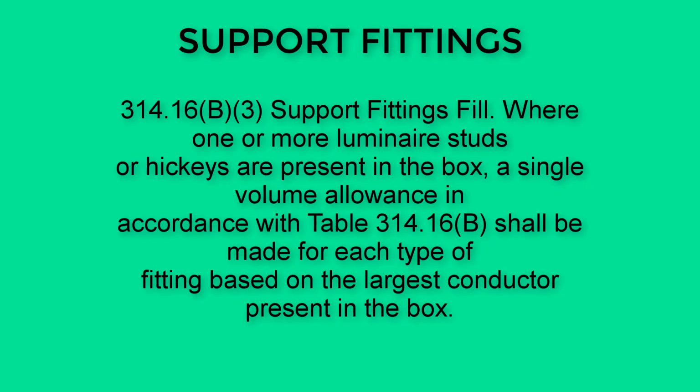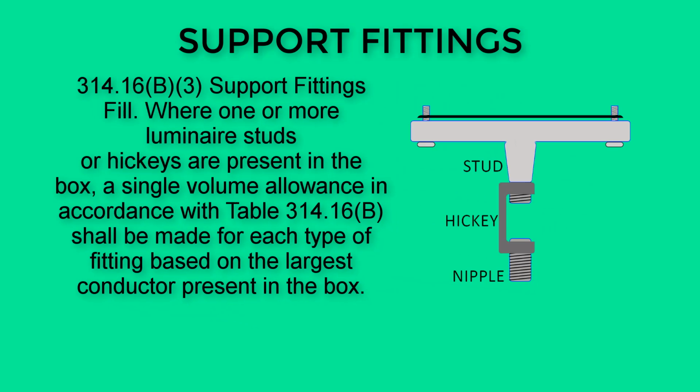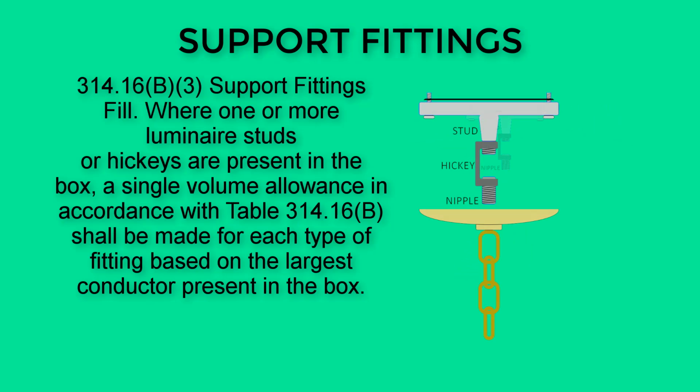Allowance for support fittings is also included in the box fill conductor count. Article 314.16(B)(3) states, where one or more luminaire studs or hickeys are present in the box, a single volume allowance in accordance with Table 314.16(B) shall be made for each type of fitting based on the largest conductor present in the box. Internal box items used for support of things like chandeliers and ceiling fans will add to the box fill count.